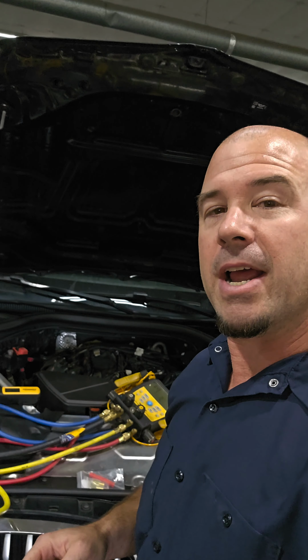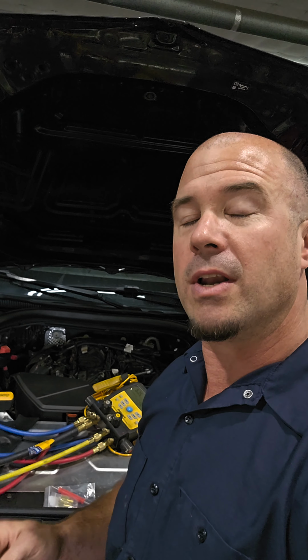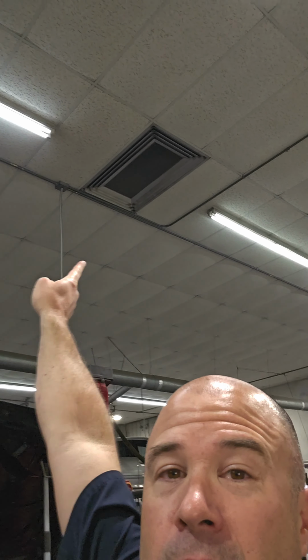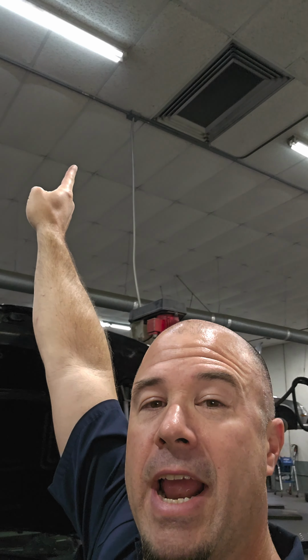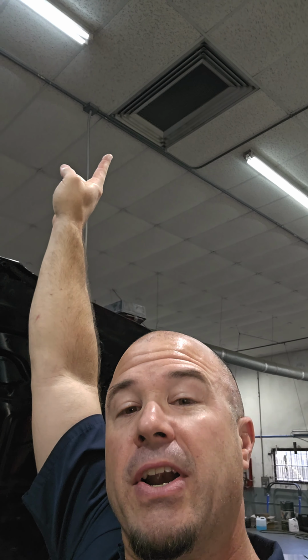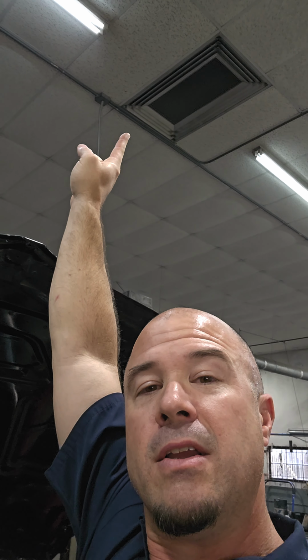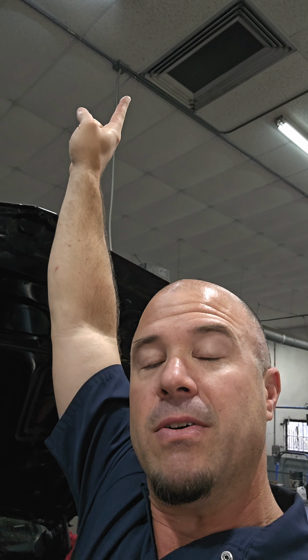Microns are 3 digits behind the decimal point, and vacuum is whole numbers. So what we do is try to vacuum down to 500 microns or less, which is weird, because those AC machines, when an HVAC technician works on your house or industrial AC systems, 500 microns is just the bare minimum of what they need to pull these things down to.